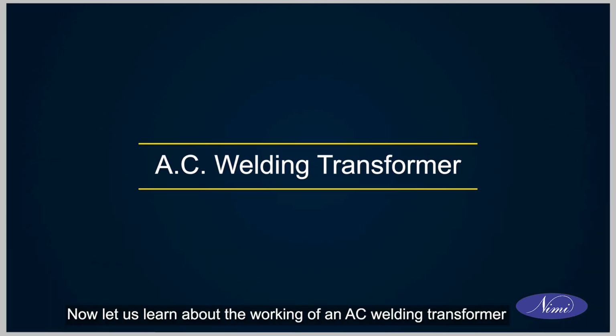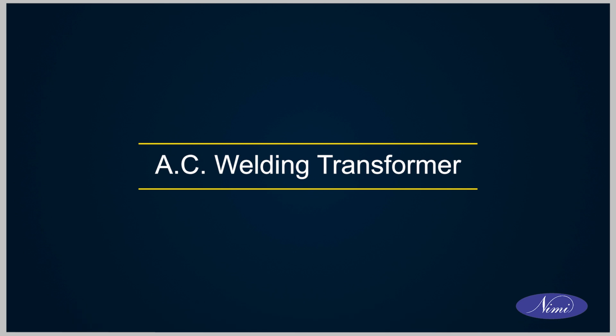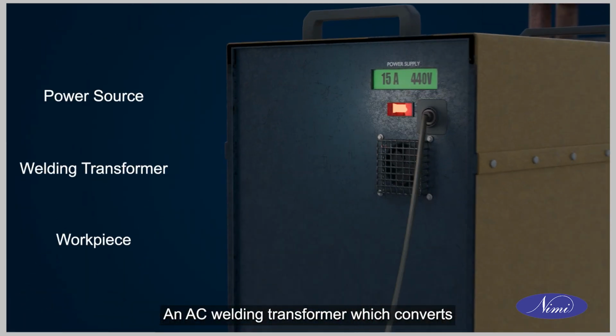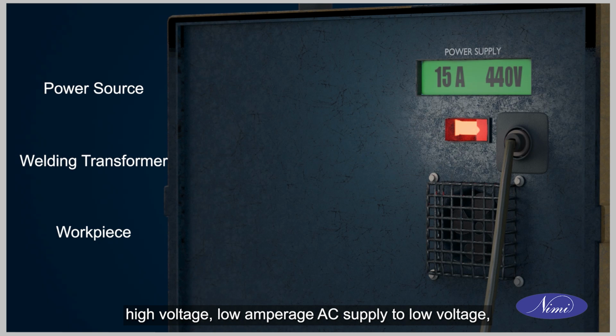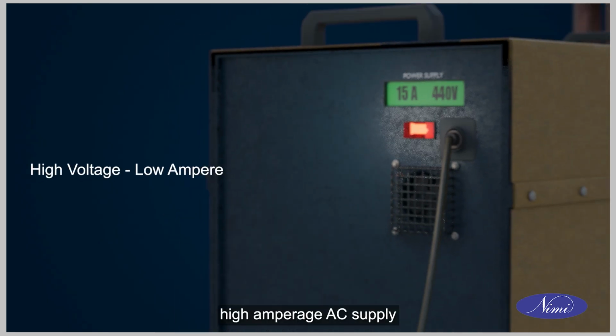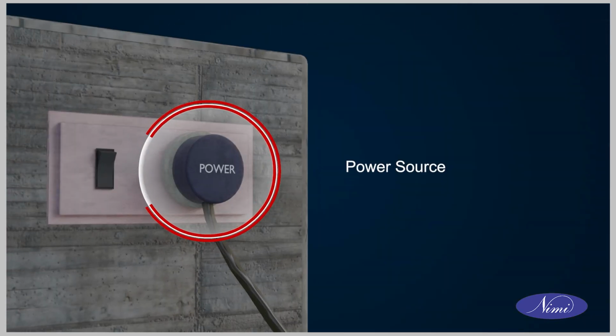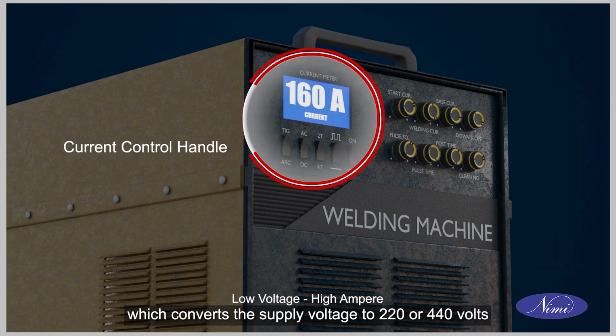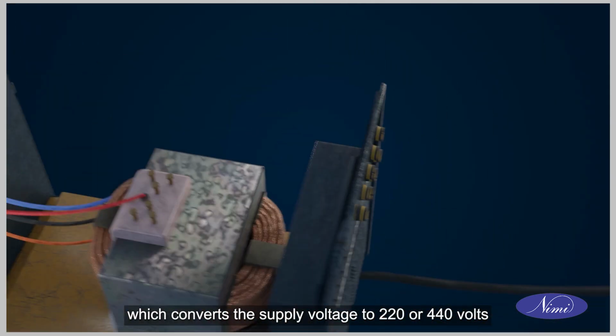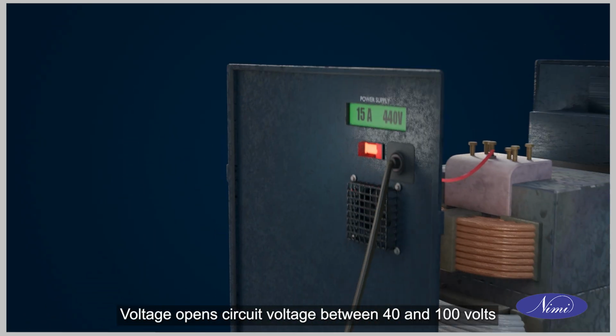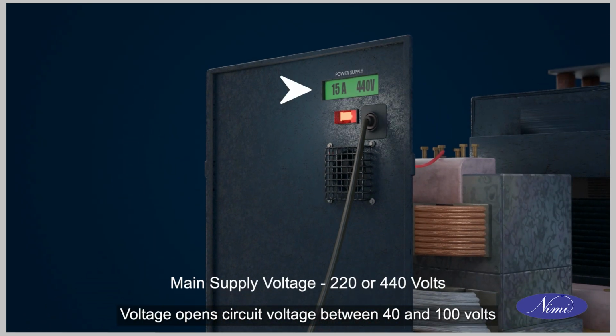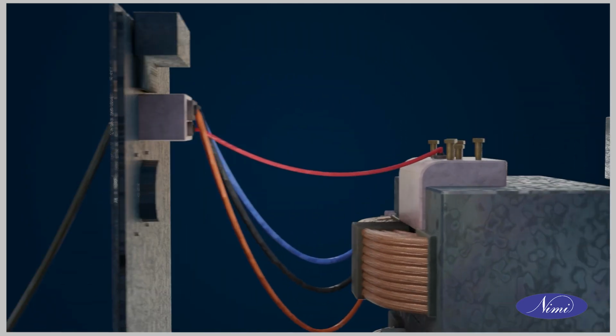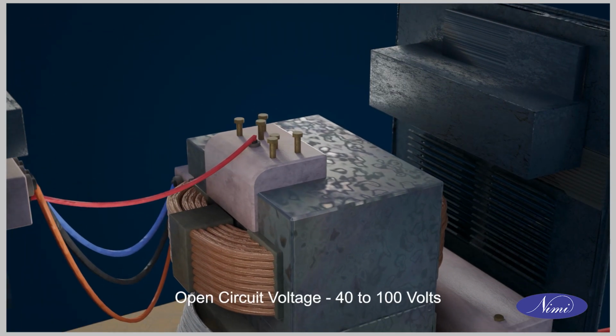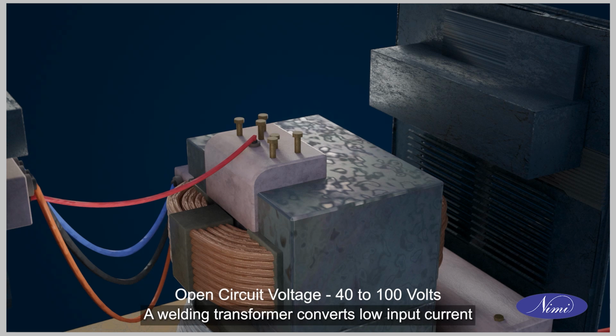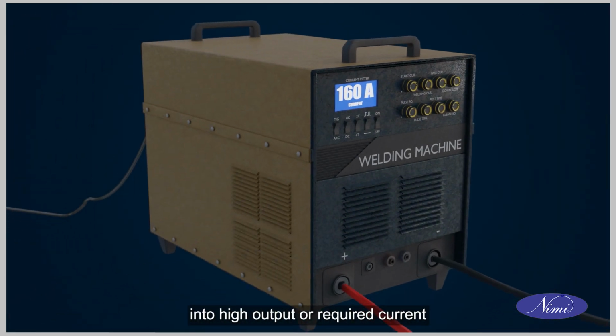Now, let us learn about the working of an AC welding transformer. An AC welding transformer converts high voltage, low amperage AC supply to low voltage, high amperage AC supply. It is a step-down transformer which converts the supply voltage 220 or 440 volts to the welding supply voltage, open circuit voltage, between 40 and 100 volts. A welding transformer converts low input current into high output or required current.